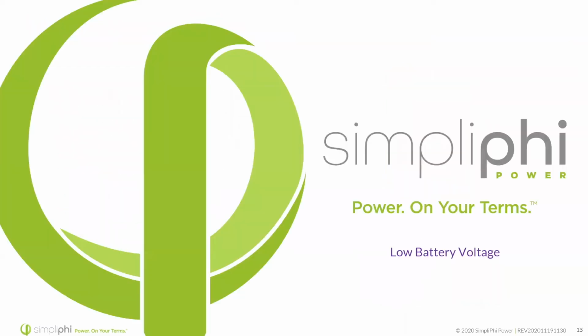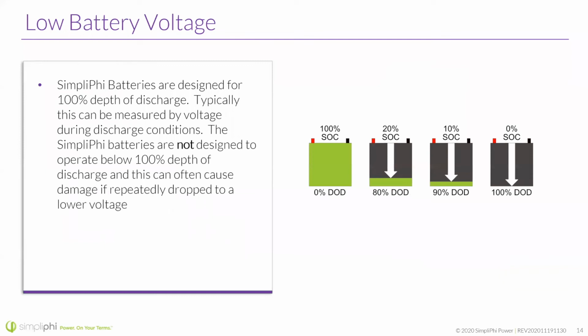Moving on to the next, I would say second most common issue, which is low battery voltage. So SimpliPhi batteries are designed for 100% depth of discharge. Typically, this can be measured by voltage during discharge conditions. The SimpliPhi batteries are not designed to operate below 100% depth of discharge, and this can often cause damage if repeatedly dropped to a lower voltage.